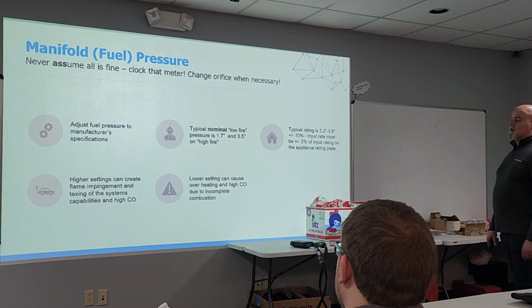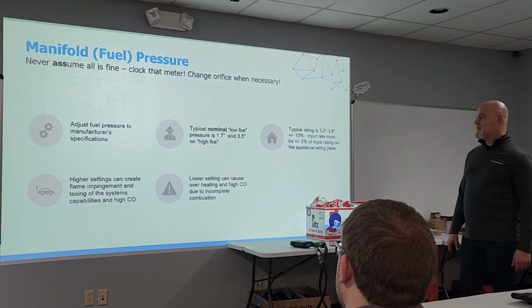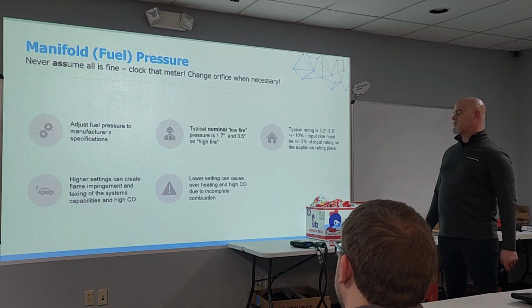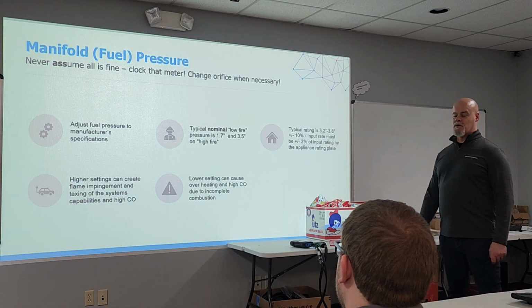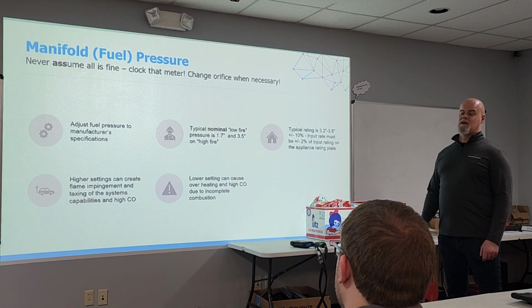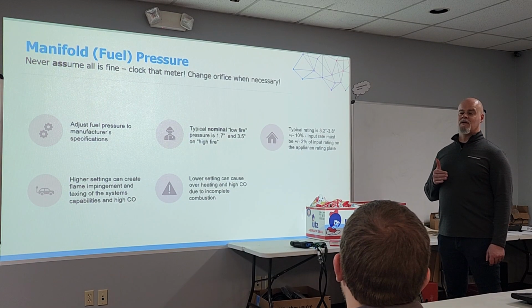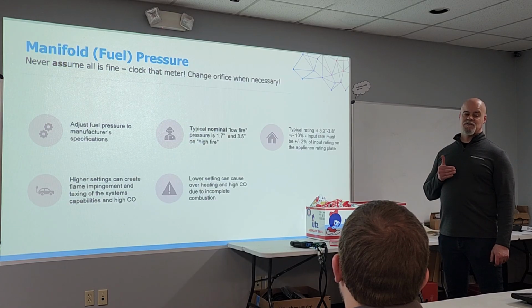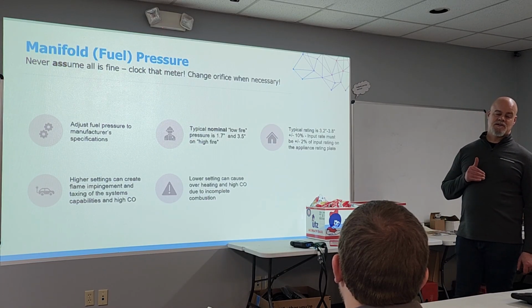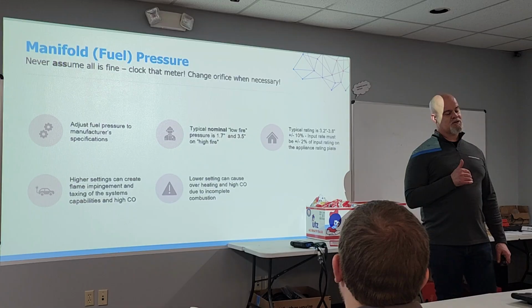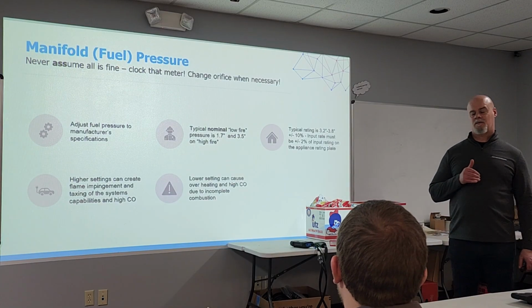So, manifold pressure. As in the words of Jim Bergman, clock the meter. Never assume all is fine. Change your orifice when necessary. Adjust the fuel pressure to the manufacturer's specifications. Typical nominal low fire rate is 1.7, high fire is 3.5. Average range that you're going to hit your sweet spot in is going to be between 3.2 to 3.8, okay?